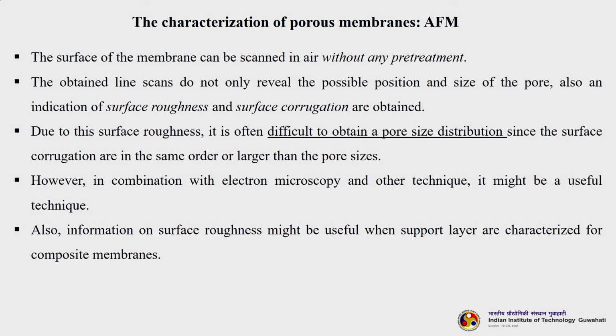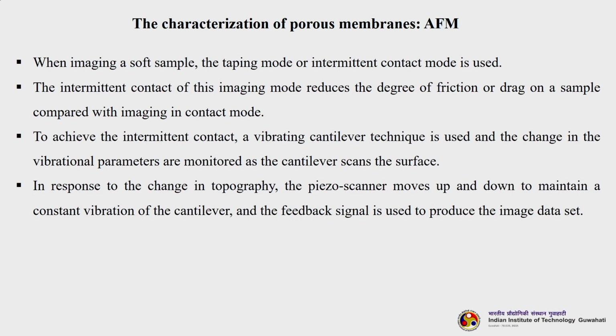So, also information on surface roughness might be useful when support layers are characterized for composite membranes. When imaging a soft sample, the tapping mode and intermittent contact mode is used. The intermittent contact of this imaging mode reduces the degree of friction or drag. To achieve the intermittent contact, a vibrating cantilever is used.